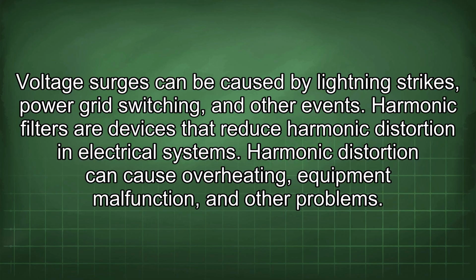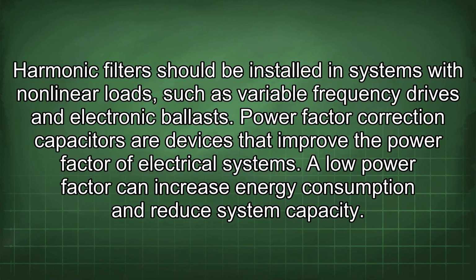Harmonic filters are devices that reduce harmonic distortion in electrical systems. Harmonic distortion can cause overheating, equipment malfunction, and other problems. Harmonic filters should be installed in systems with nonlinear loads, such as variable frequency drives and electronic ballasts.